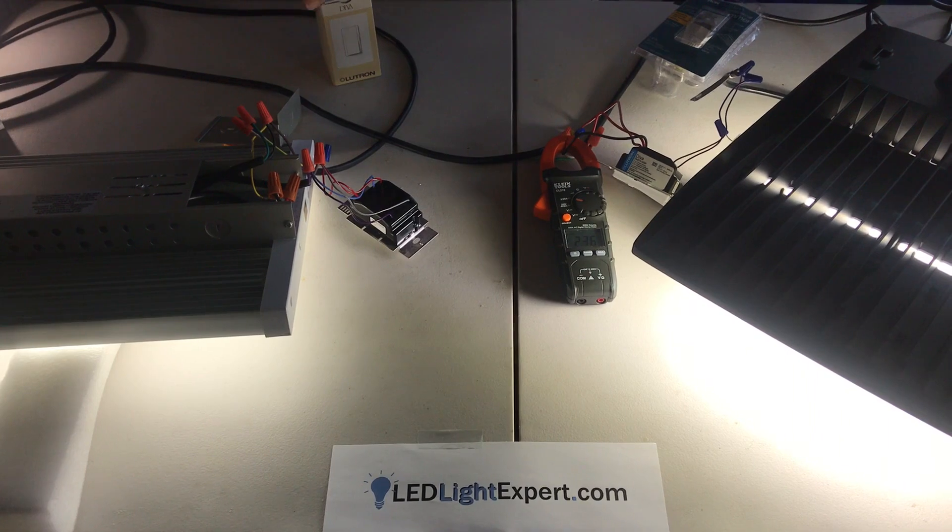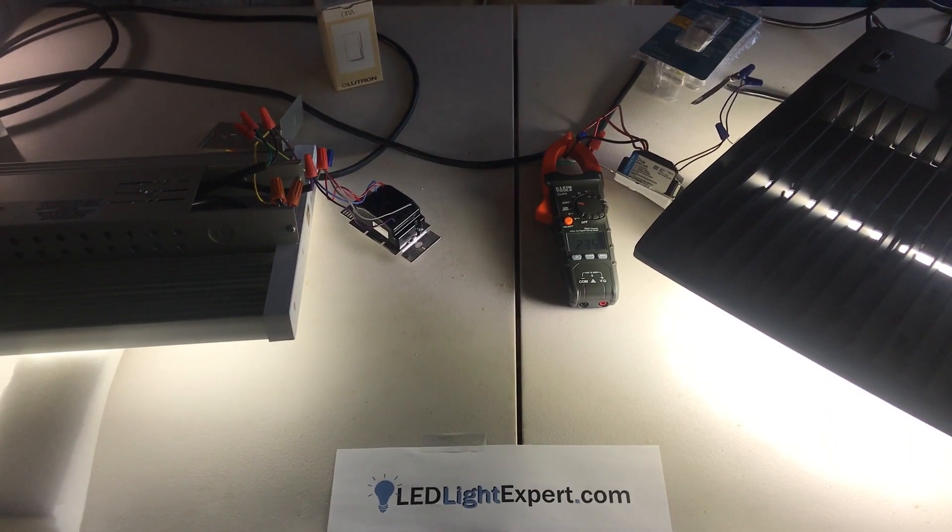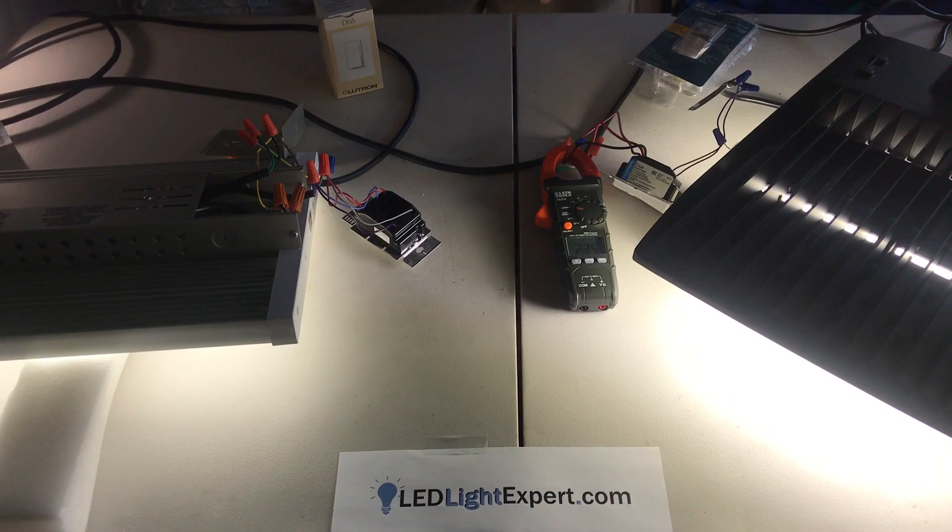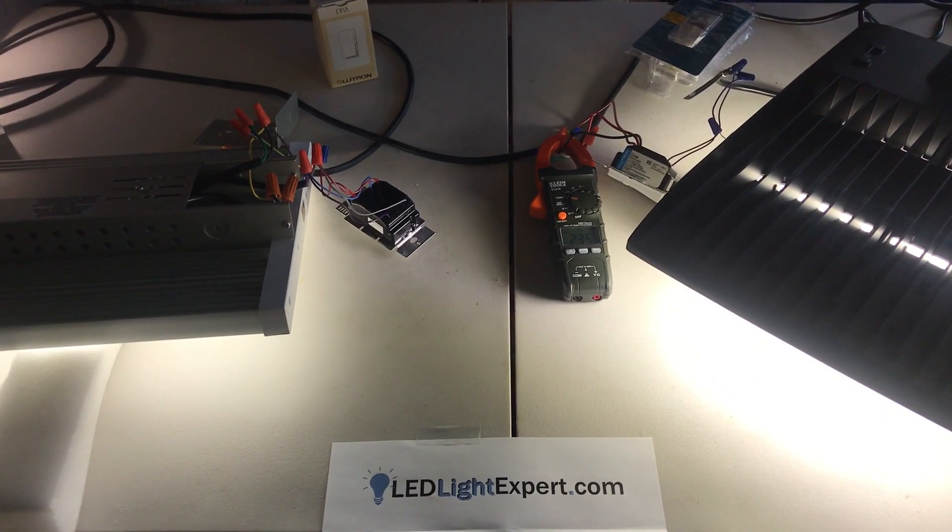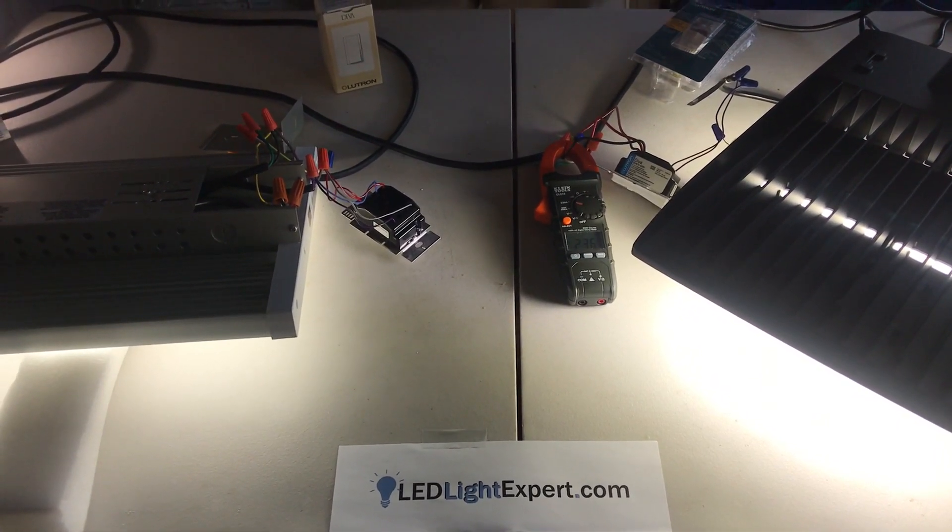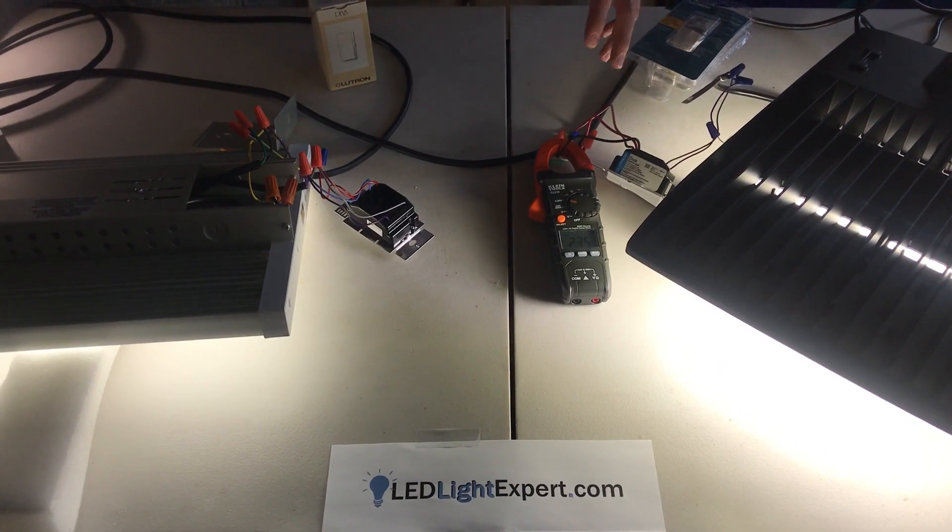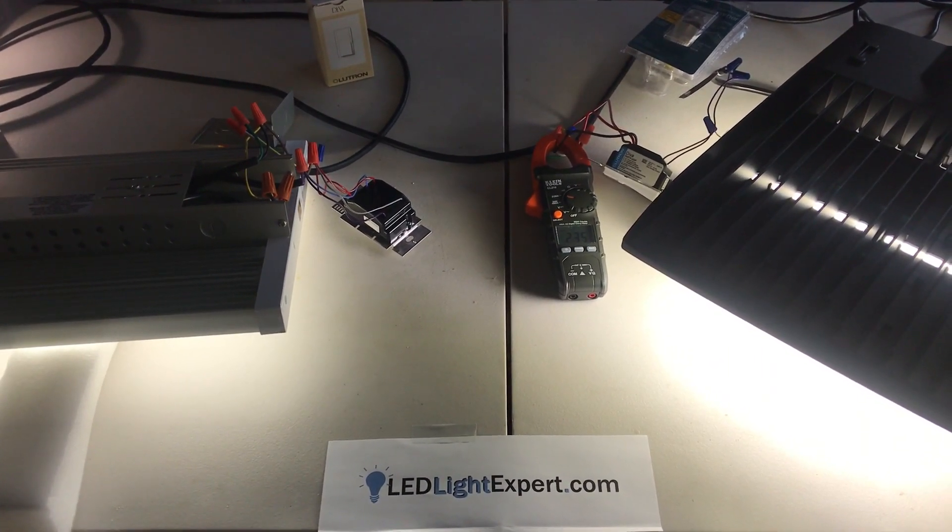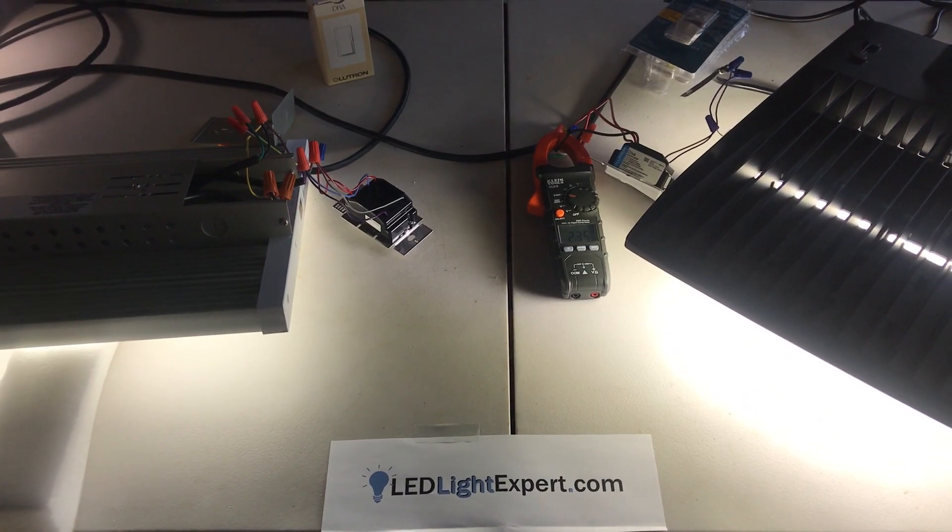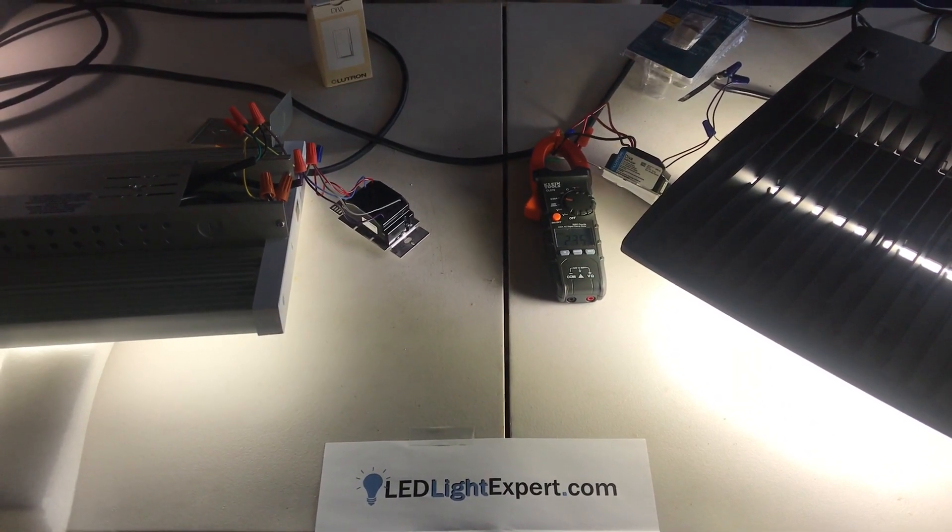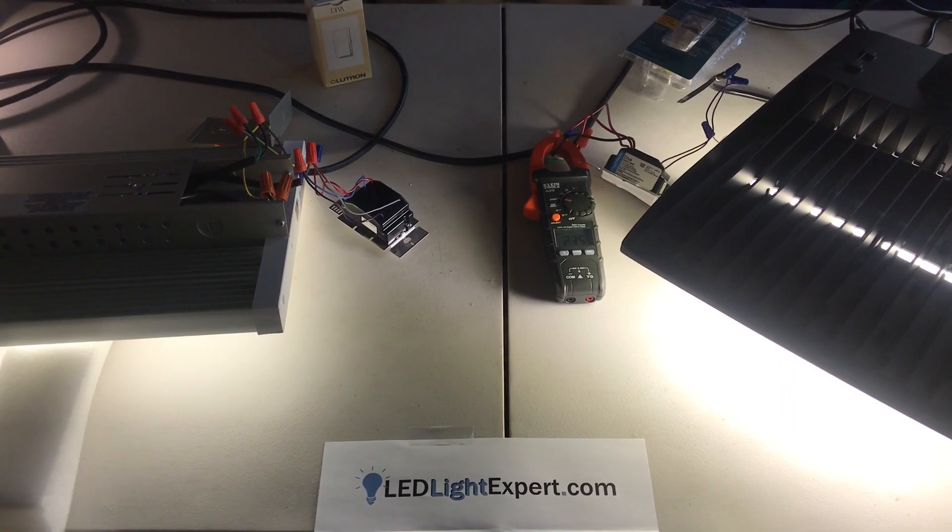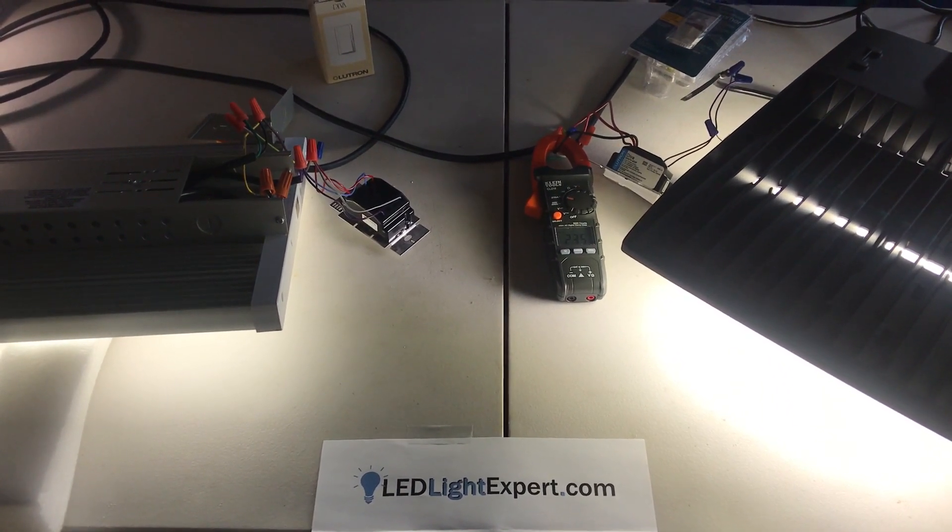They do have a higher one that's 8 amps, probably a few others out there a little bit higher. But keep that in mind when planning how many fixtures can you put per switch. Theoretically the 0 to 10 volt stuff can handle about 20 fixtures and 200 feet of run before you start to get into some problems. But the reality is you're probably going to run into power restrictions before you do that.